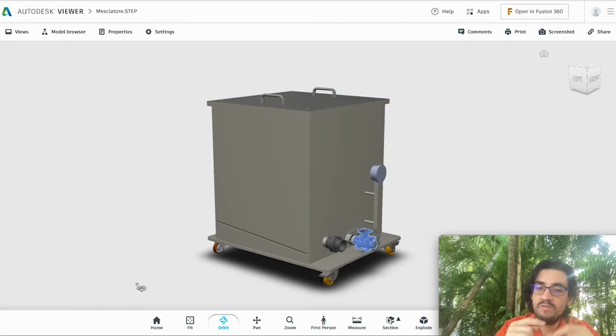When you're doing a continuous filtration pattern, there's a lot of accessories that you can connect to the outlet to monitor that fluid that's going through that pipe. And with a spectrometer, what you can do is identify the extraction endpoint. Not only can you identify the amount of trichomes that are being removed, to give you a really good idea when you're done extracting the bulk of the trichomes, but also the production of contaminants like chlorophyll, things like that. So your trichomes in your graph are going to be coming down and your contaminants are going to come up. So it's going to be like a cross section, a point of diminishing returns when it's no longer feasible to continue operating. And instead of stopping a batch and trying to identify that, you can visually see that representation of the process happening. So we think that's definitely a winner.